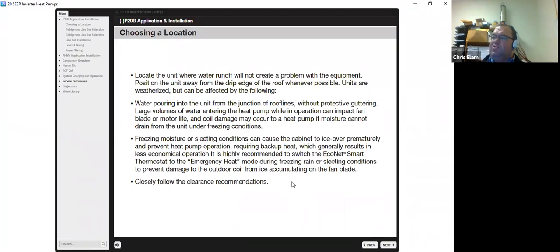Freezing moisture or sleeting conditions can cause the cabinet to ice over prematurely and prevent heat pump operation, requiring backup heat. Also, what can happen if the top does ice over during an off cycle and it does turn on, it will shake violently and could end up breaking the fan blade and causing damage to the coil. So if you ever come across one that the customer complains it's shaking very violently in heating, chances are the fan blade could have ice on it. It is now off balance.